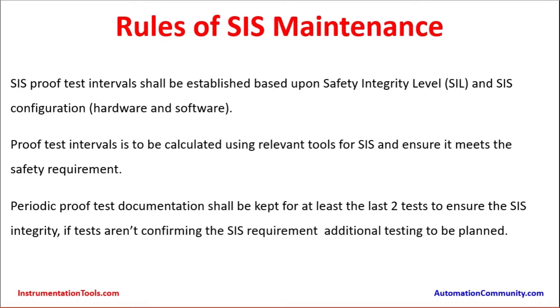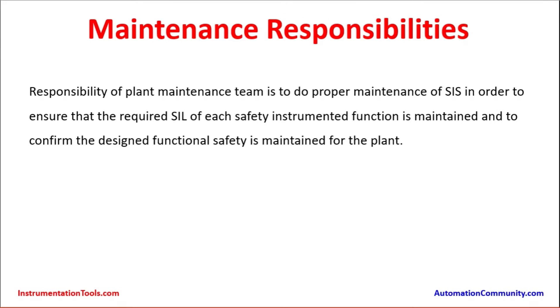The responsibility of the plant maintenance team is to perform proper maintenance of the Safety Instrumented System, in order to ensure that the required SIL of each Safety Instrumented Function is maintained and to confirm the designed functionality and safety is maintained for the plant. Maintenance has the responsibility to do the testing at the proper intervals.